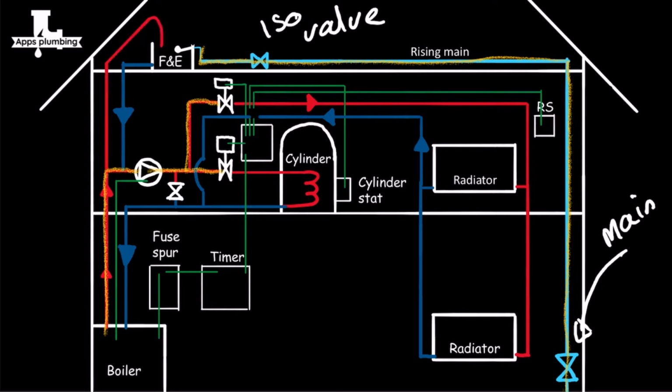So what happens is, when this water expands, it goes up. It expands up the tube or up the 22mm pipe. That needs to be 22mm, guys. All right. If that's 15mm, then obviously you won't get enough expansion, and the water will just eventually keep going up and up and up, and then going into your F&E tank. Okay. So that's called our feed and expansion.